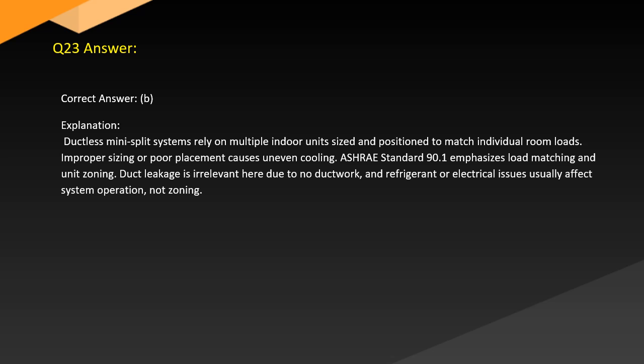Answer. Correct answer: B. Explanation. Ductless mini-split systems rely on multiple indoor units sized and positioned to match individual room loads. Improper sizing or poor placement causes uneven cooling. ASHRAE Standard 90.1 emphasizes load matching and unit zoning. Duct leakage is irrelevant here due to no ductwork, and refrigerant or electrical issues usually affect system operation, not zoning.